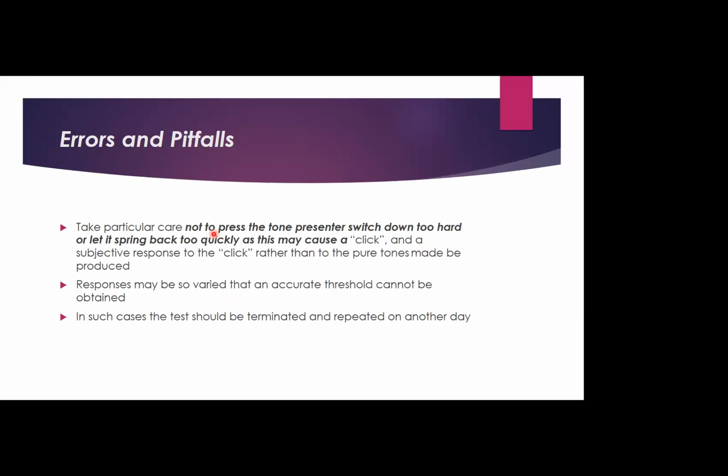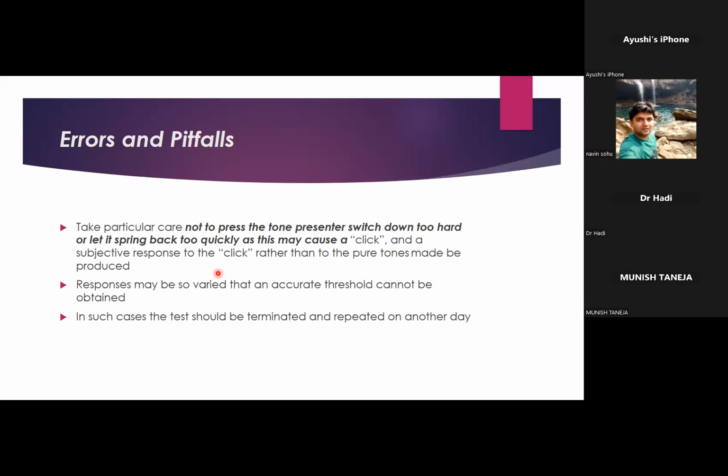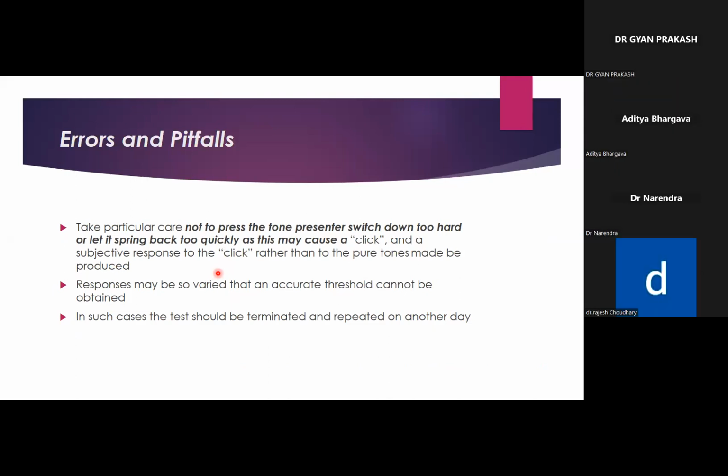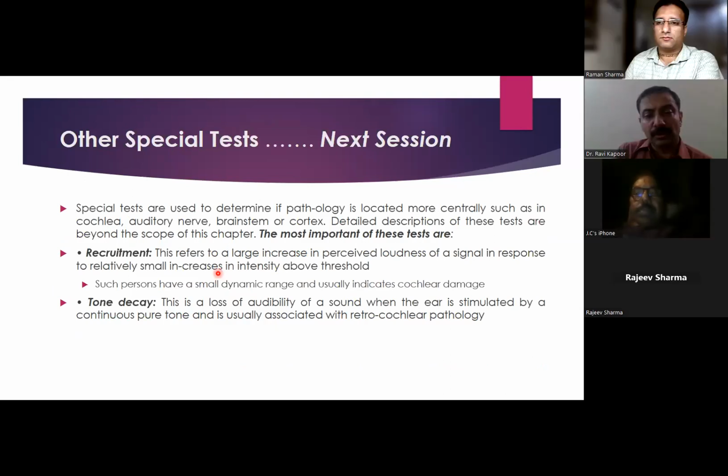Do not press the tone presenter switch down too hard or let it spring back too quickly, because that might cause some clicking sounds. That may again be misleading and cause false responses. The other special tests which include pure tones, the recruitment test and tone decay, we'll be discussing in our next session. These also utilize pure tones.